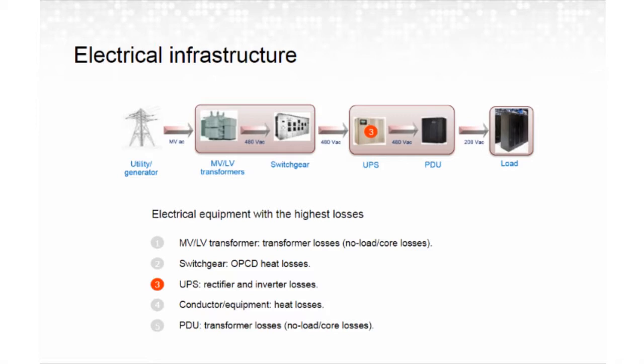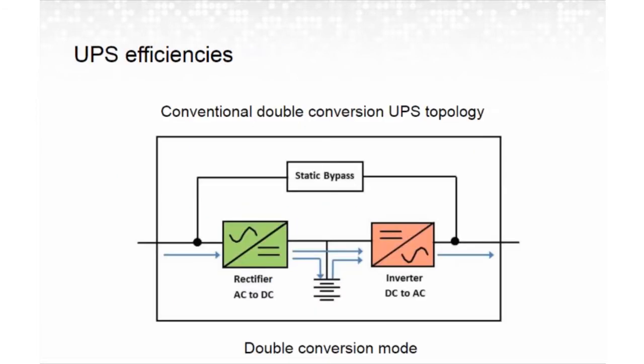So the next piece of the infrastructure that creates losses is the uninterruptible power supply, or UPS. When we look at a conventional double conversion UPS technology, we have the incoming power going through a rectifier, so it converts it from AC to DC, so some losses are associated with that. Then as it goes through and charges the battery, it comes out the other side through the inverter, which converts it back from DC to AC to the load. So in both of those conversions, we do get a little bit of loss of power.